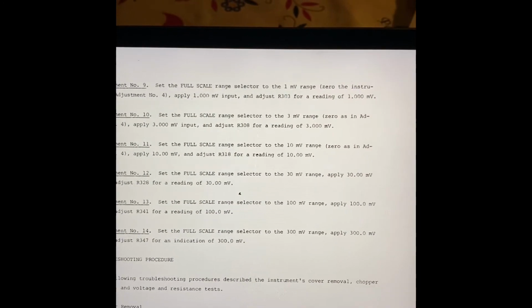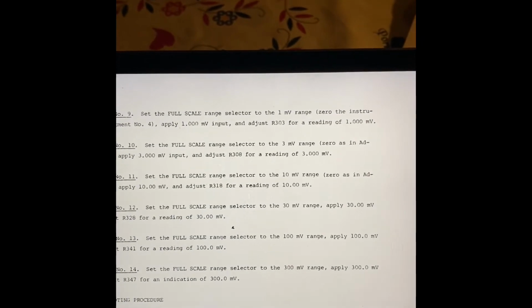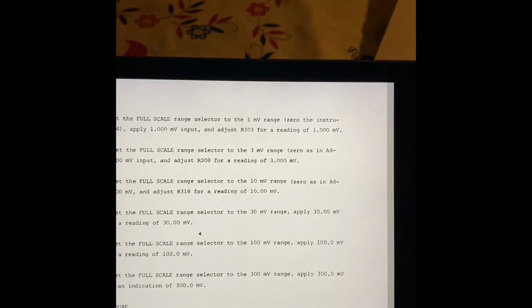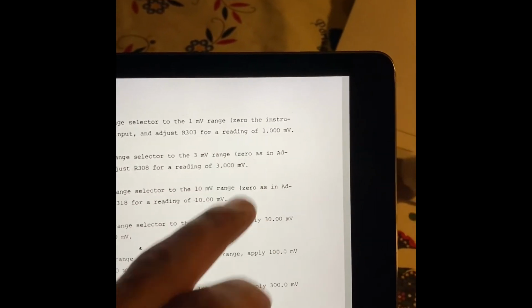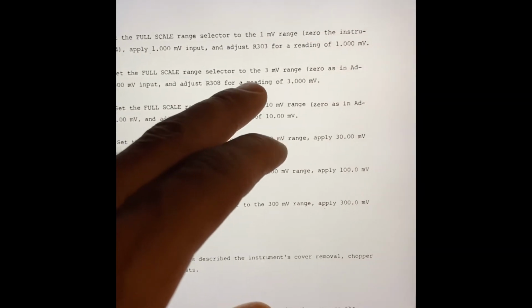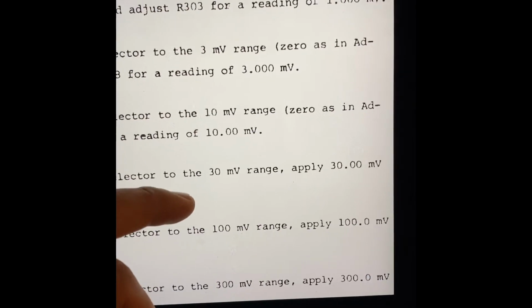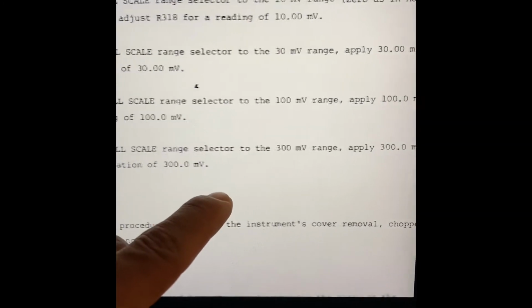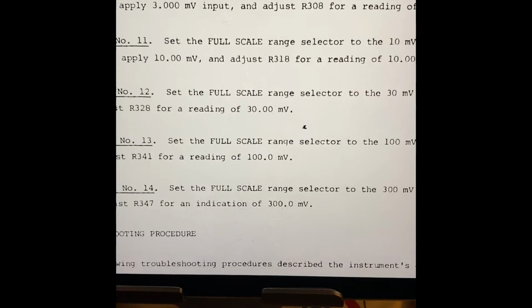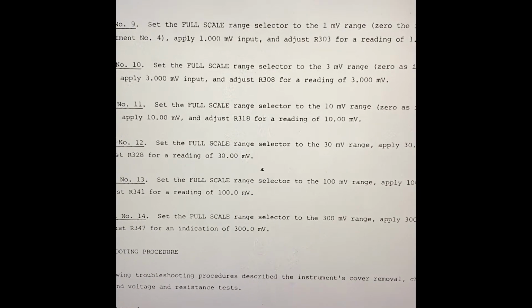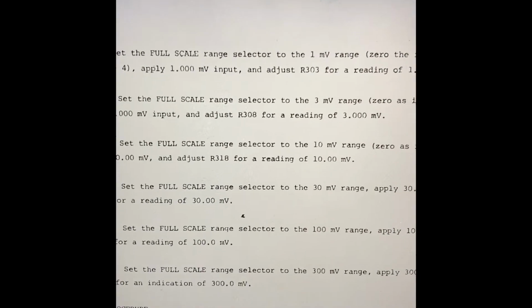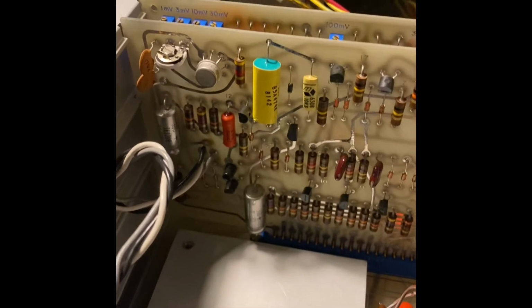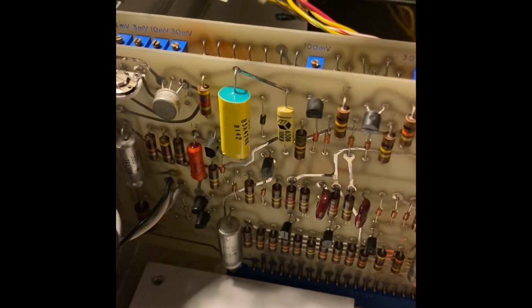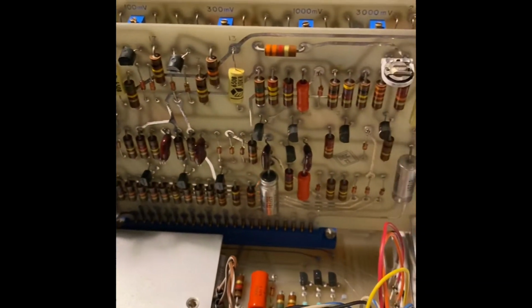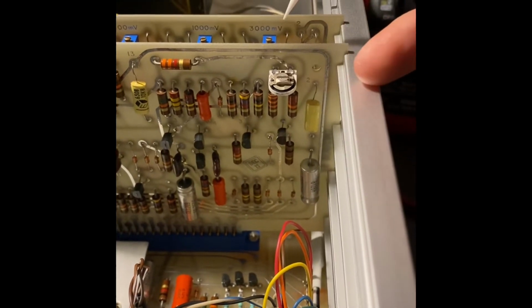Okay, so basically now I have to zero the instrument to 1 millivolt range, and then we input 1 millivolt and adjust the 303 as I said, and then in turn we'll go through the next ranges. We go to the 3 millivolts, to the 10 millivolts, 30, 100 and 300, and we do all the same things, just we will use the appropriate adjustment over the board, which will be 1, 3, 10, 30, 100 and 300. Then we stop here. We will have finished because we started with 1000 and 3000.